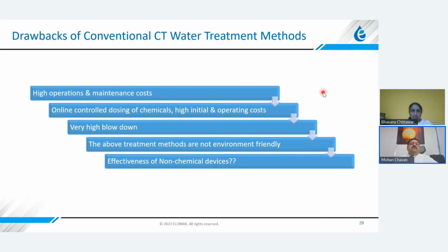Let's look at the drawbacks of conventional water treatment methods. The first and foremost is high operations and maintenance cost. Online controlled chemical dosing has high initial cost as well as operating cost. Plus, there are safety issues also, because these chemicals need to be handled, and the chemicals are hazardous. Sometimes they are using acids, and handling is really a hazardous task in the industries. So to maintain the parameters in the cooling water sump, there is high blowdown that needs to be given continuously. The above treatment methods are not environment friendly, because we add chemicals and we do the blowdown to maintain the TDS or conductivity in the cooling tower sump. And the effectiveness of non-chemical devices is really questionable.